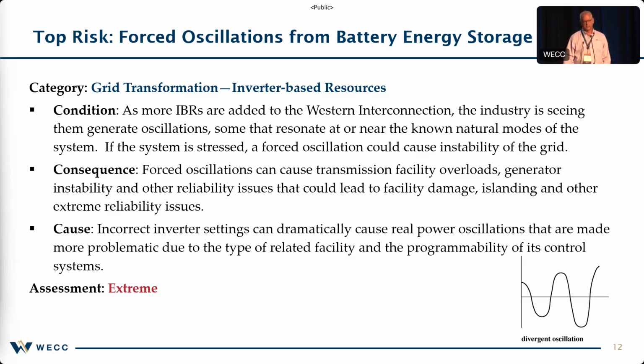We saw a forced oscillation in the Eastern Interconnection a couple of years ago from a 75 megawatt combustion turbine in Florida that caused massive power flows on the 500 kV systems out of Florida and propagated all the way across the Eastern Interconnection. So I've heard stories of 700 megawatt batteries in the West -- that's a 1,400 megawatt impact. That will cause some damage if it's not properly operated, programmed, and controlled. So we feel this is one of our most extreme risks coming at us in the near future, after seeing some of the events that actually occurred during testing.